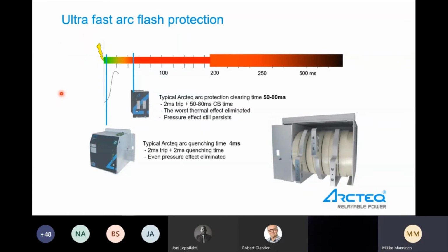But it is good. But this is the only one which can be fully tested. You can recharge it and test the device 100 times. Of course, it is very important to have the commissioning mode. In these terminals here, there is a commissioning input, and if you don't use that commissioning input, you can only use this device twice. So it is very important to know.